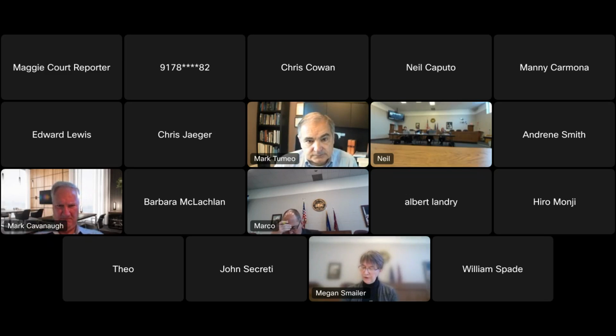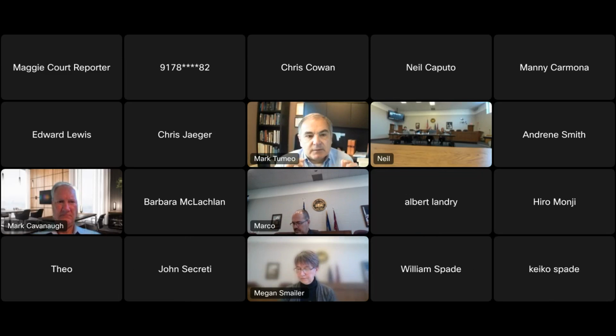Okay. So it's just a voluntary change of system. Yes, it's a risk reduction technique. And could you explain what might cause the accidental discharge? Yeah, there's actually several reasons. Most of them are mechanical, because unlike a closed head system that's based on the existence of a fire, these systems are tripped by either detectors or mechanical systems, either a hand pull system or some kind of electronic detector that's looking for something that looks like flame.